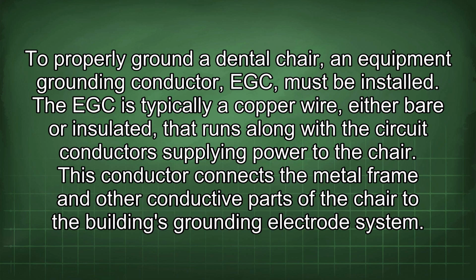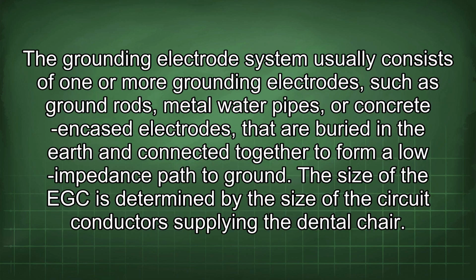To properly ground a dental chair, an equipment grounding conductor (EGC) must be installed. The EGC is typically a copper wire, either bare or insulated, that runs along with the circuit conductors supplying power to the chair. This conductor connects the metal frame and other conductive parts of the chair to the building's grounding electrode system. The grounding electrode system usually consists of one or more grounding electrodes, such as ground rods, metal water pipes, or concrete encased electrodes that are buried in the earth and connected together to form a low impedance path to ground. The size of the EGC is determined by the size of the circuit conductor supplying the dental chair.